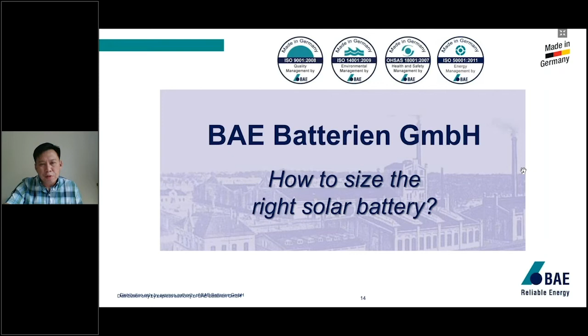So how to size the right solar batteries? This is a question that comes up a lot. Normally, in order for us to size the battery, we need you as a customer to provide some information. First, you need to decide what type of batteries you want to use, vented or sealed type, and installation - horizontal or vertical. Do take note, horizontal or vertical is only applicable for sealed batteries; vented cells must be vertical, there's no way to put them horizontal, the acid will leak. Also, the system voltage.